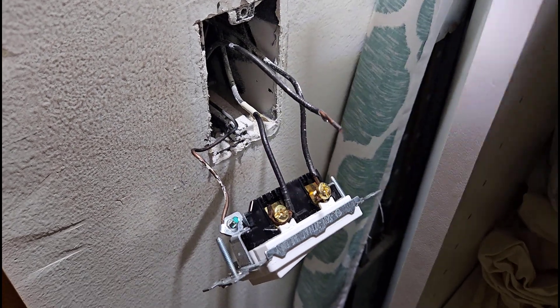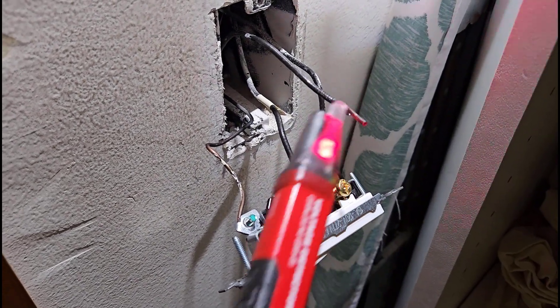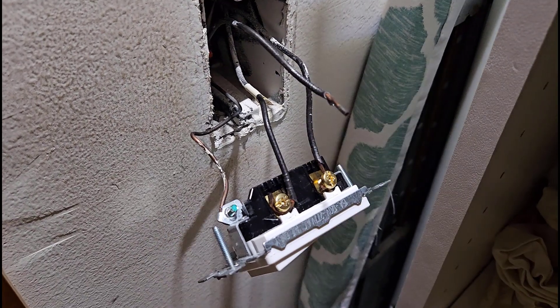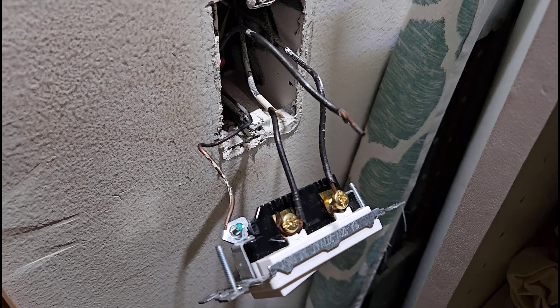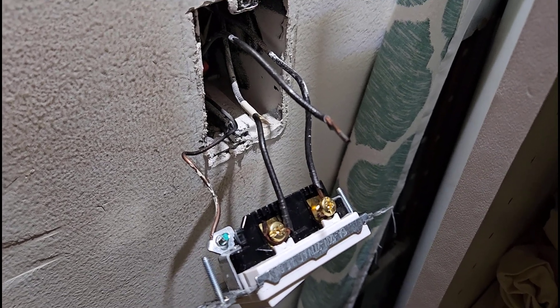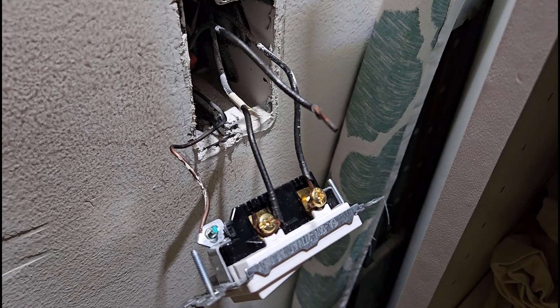So we now have the breaker back on and you can see that this wire here is live, so whoever wired this previously was effectively using the switch as a junction box and then had another wire running off to power something else which again is a no-no. So we're going to show you the proper way to do it.